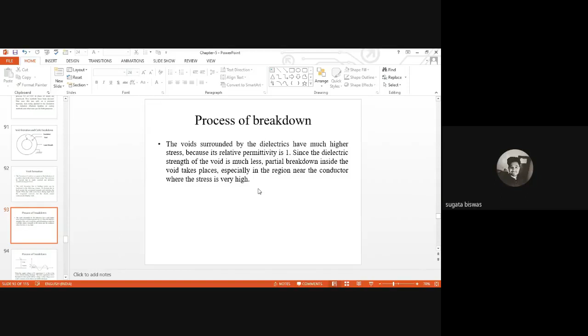Yes, sir. Now, the question is how repeated flashover or arcing takes place inside the cable. It is because air is a self-restoring type of insulating material. What is a self-restoring type of insulating material? An insulating material which can regain its dielectric strength when the cause for the sparkover or arcing is withdrawn. Now, what happens when an arc occurs for the first time? There is complete ionization of the air bubble or the void, resulting in a fall of voltage across the void. The voltage across the void becomes zero.